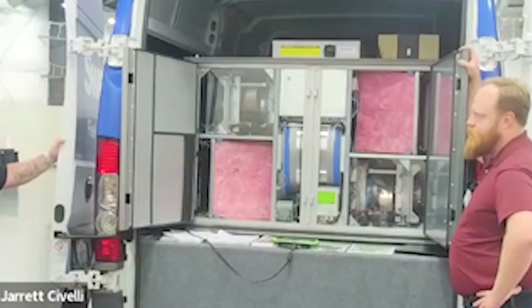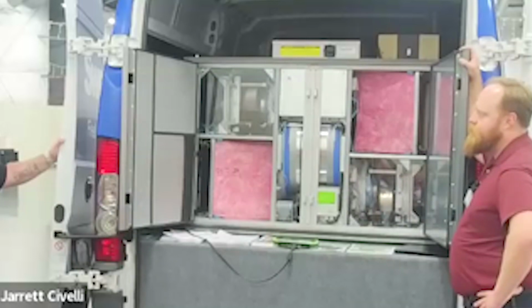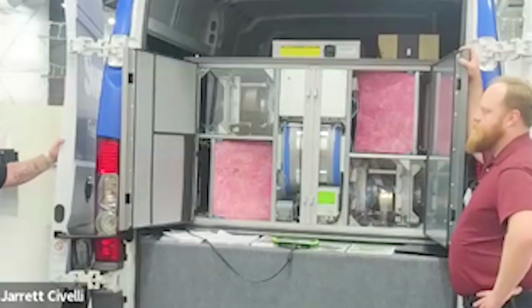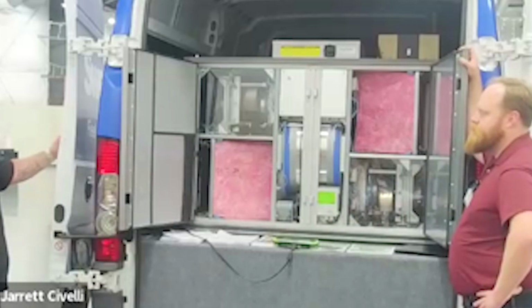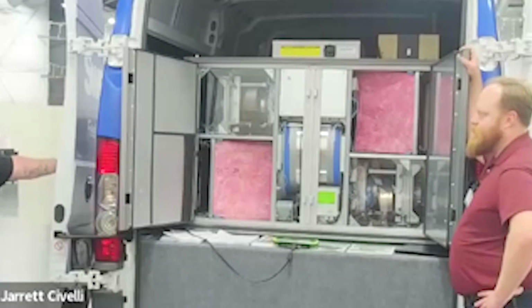I don't know if I'm supposed to name names - forgot it already. So they had a wheel heat exchanger that served their lobby and locker rooms off of the pool. That wheel didn't handle the corrosive air coming in from the pool area. The staff would prop the doors open and all that humid, chemical-laden air would hit that wheel. That's the only one in 20 years or so that I've heard actually failed, because of air quality.